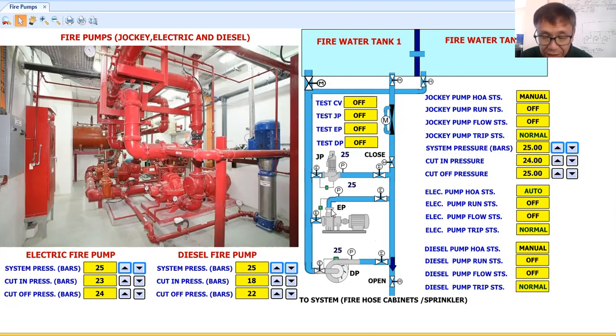Now here, as you can see in the fire pump room, there will be several valves. There will be a pressure regulating valve and control zone valves, and all these valves will be monitored in the fire alarm system. When I say monitored, they will monitor whether it is in the closed or open position. Let's say someone tries to repair this jockey pump, then they have to close these valves. It will be monitored in the fire alarm system that the valve was closed, so there will be a trouble alarm in the fire alarm panel. So it will always be recorded that the valve is closed.